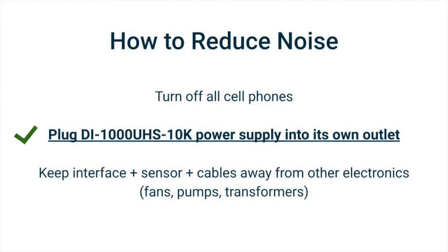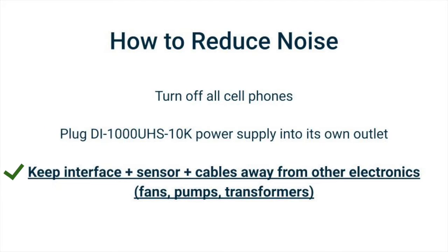Plug the interface power supply into its own outlet. There shouldn't be any other electronics sharing the same electrical outlet. Keep the interface, sensor, and cables away from other electronics, like fans, pumps, and transformers.